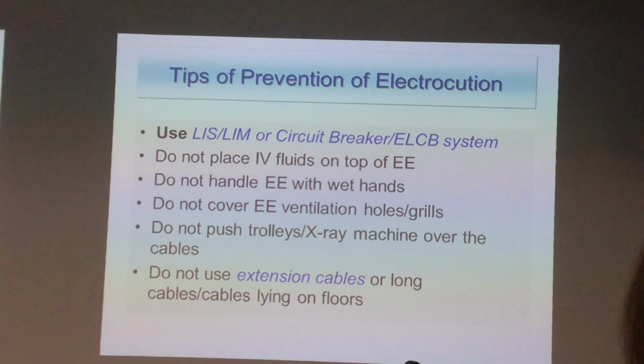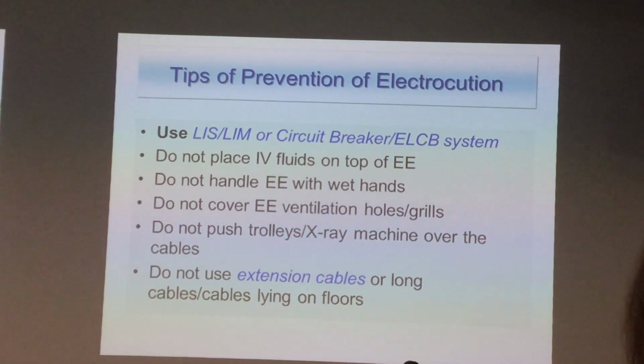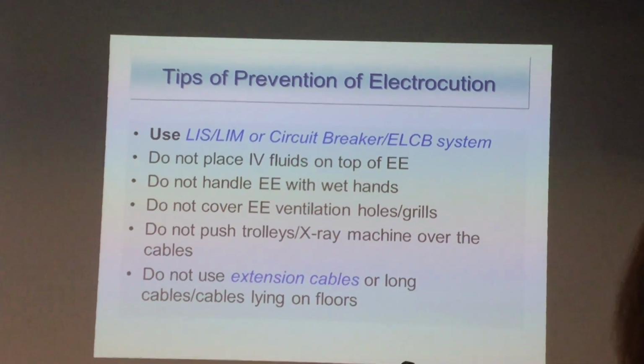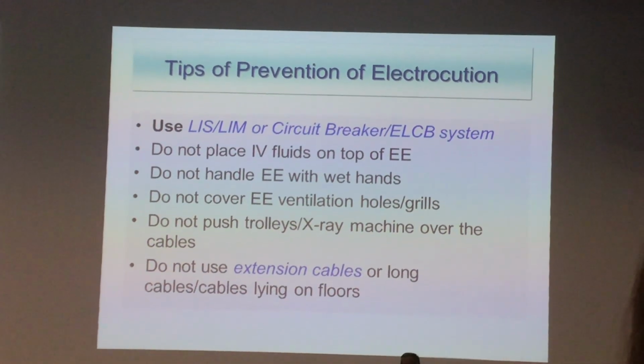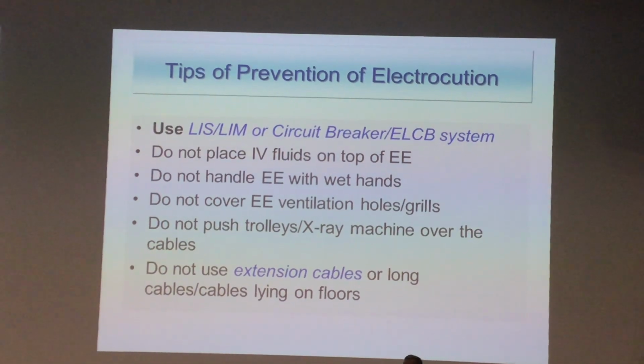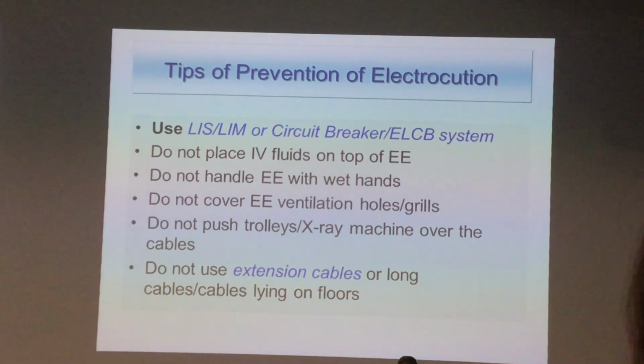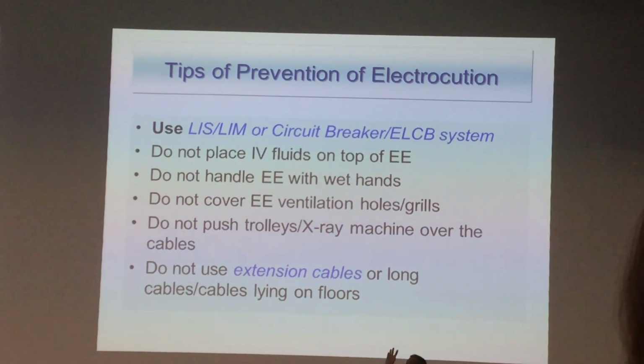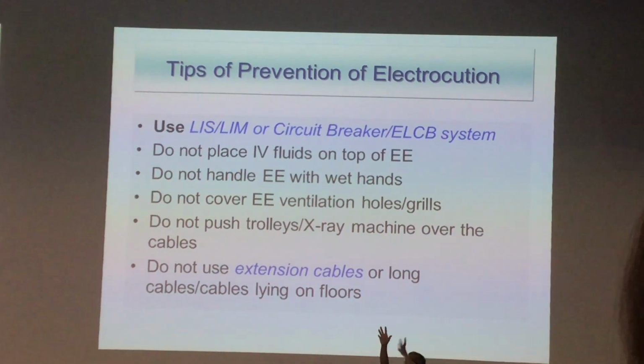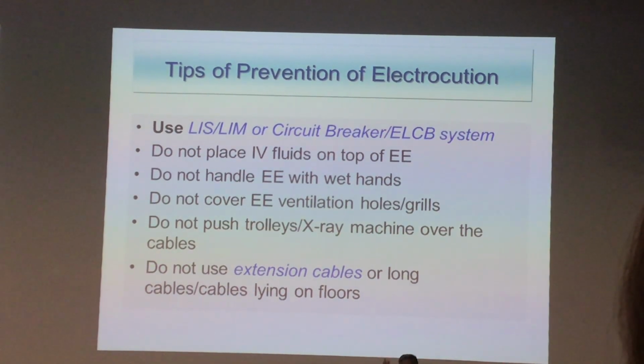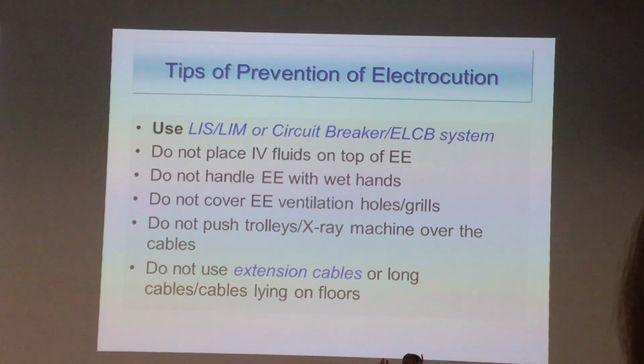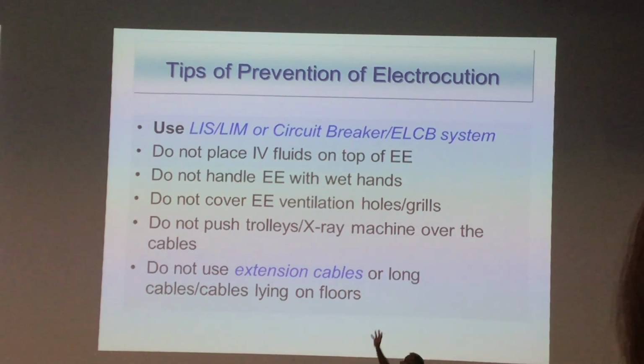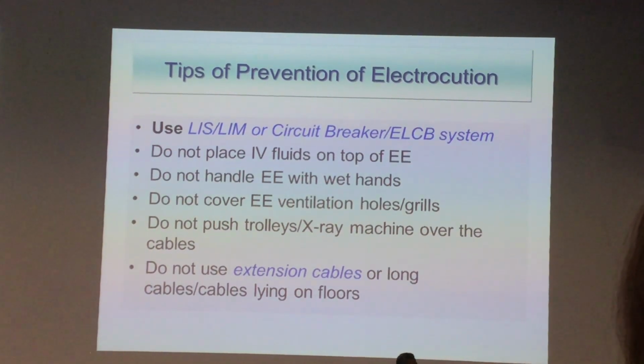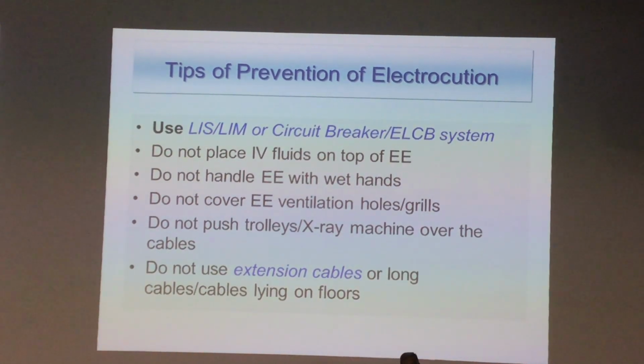Do not use extension cable or plug. Never ever. But we are doing it every day. We shouldn't do that. I think it's our culture to use extension cables simply because we have a wrong design for OT. That's why you need a good design for your OT. You don't need cables. You have to work out how many sockets you want in that pendant before constructing the OT, to avoid using extension cables. So the electrical points should be on the pendant, not on the wall. Try to avoid the wall socket. Must be pendant, so everything comes from the top down.